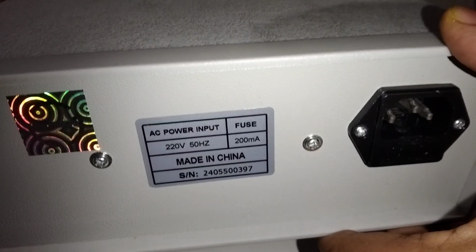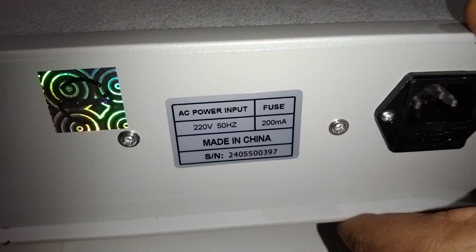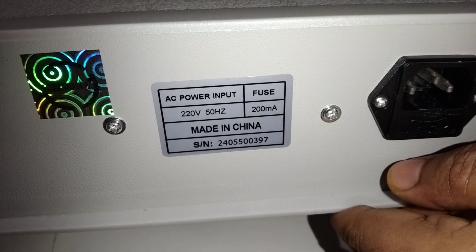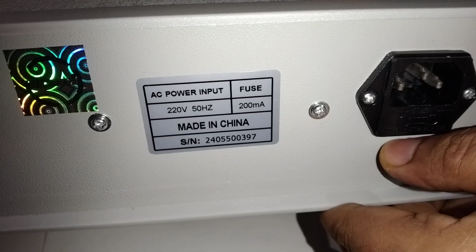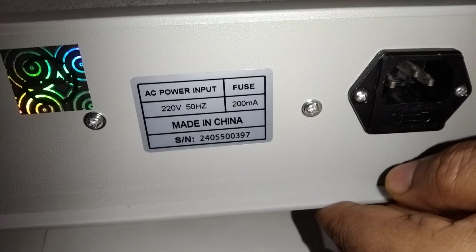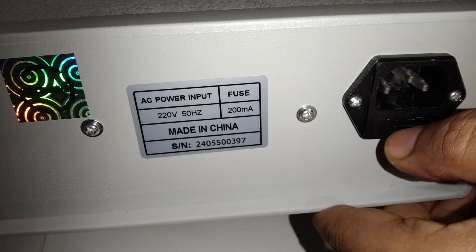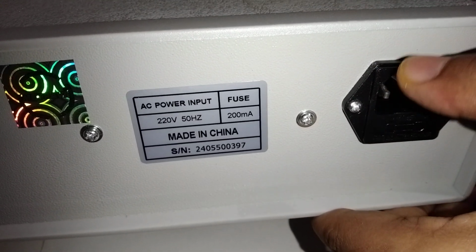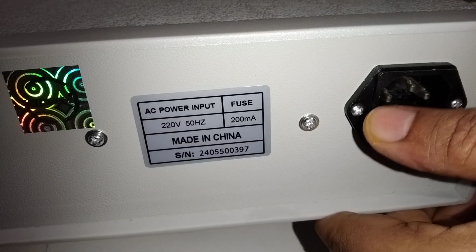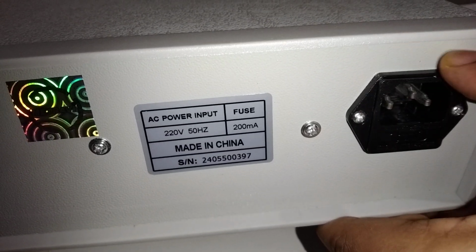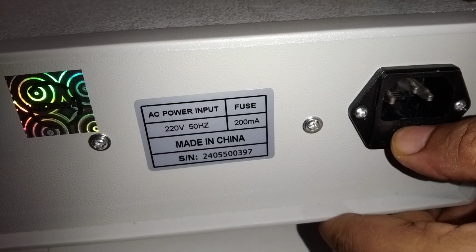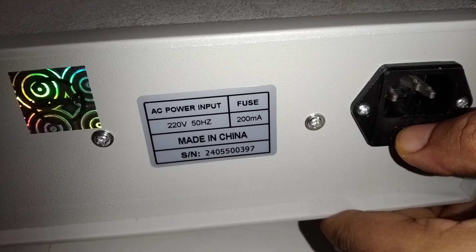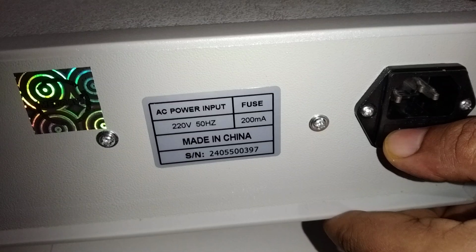So by chance if you encounter a problem that the instrument is not switching on, even if you press the power on button, and the display is not working, or you are not getting output from the output port, in that case the diagnosis begins from the power supply, that is, whether the instrument is receiving the power supply or not. So you have to first ensure that the power cord is connected. Then second, you have to check the fuse over here, whether the fuse is there or not, whether it has blown or is working fine.